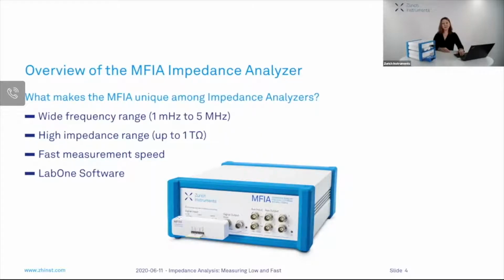We avoided the traditional auto-balance bridge, and thanks to this refreshed architecture, we could open up the frequency range, impedance range, and vastly improve the single-point measurement time. I should also not forget about the software LabOne that we developed from scratch, allowing you to fully control your setup. You will see a lot of LabOne today.